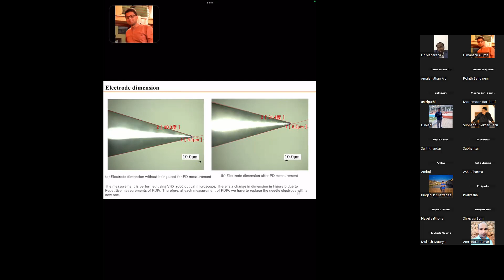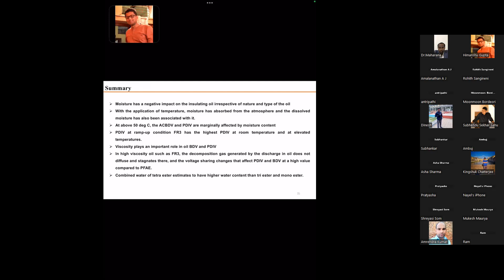So in summary, moisture has a negative impact on the insulating oil irrespective of the nature and type of the oil. Definitely, whether it's a mineral oil, ester oil, or synthetic ester, moisture in the oil is very dangerous. With the application of temperature, moisture is absorbed from the atmosphere, and the dissolved moisture has also been associated with it. Already we had moisture and we put some moisture and we measured it. Above 50 degrees centigrade, BDV and PDIV are marginally affected by the moisture content.